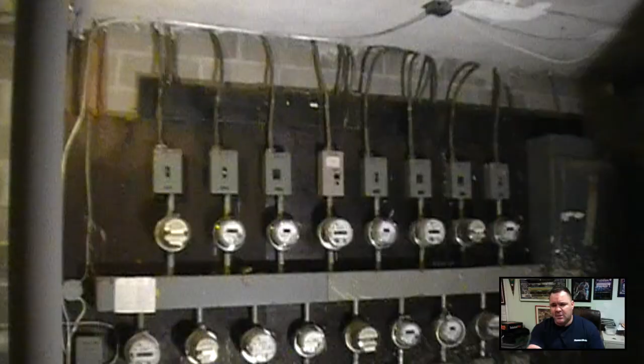So here I am testing to make sure we've got the proper voltage. Should have 120 volts to ground on each leg, and of course 240 volts across the legs, and that's what I'm testing for here.